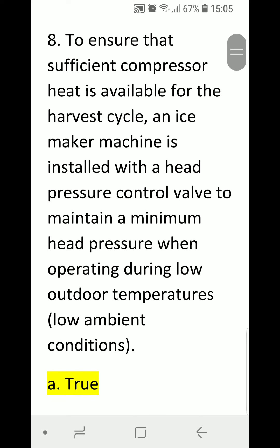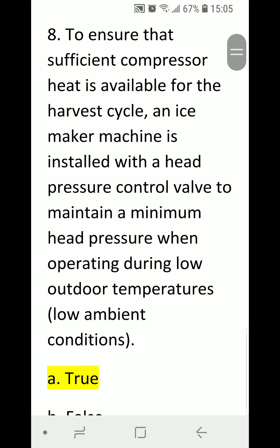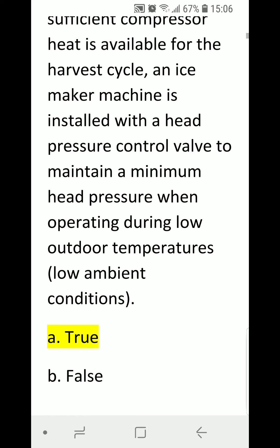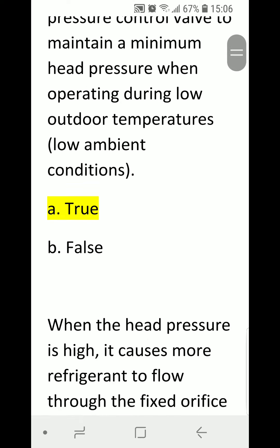Number eight: to ensure that sufficient compressor heat is available for the harvest cycle, an ice making machine is installed with a head pressure control valve to maintain a minimum head pressure when operating during low outdoor temperatures and low ambient conditions. A) true, B) false. Correct answer is A, true.